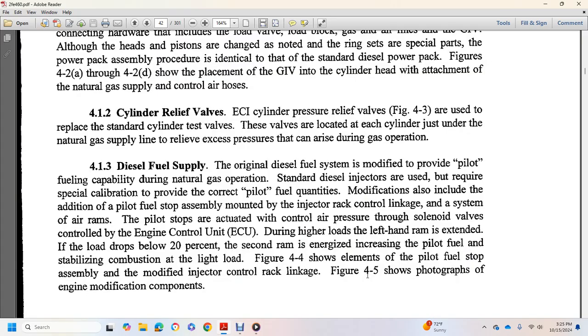4.1.3 The diesel fuel supply. The original diesel fuel system is modified to provide pilot fuel capability during natural gas operations. Standard diesel injection is required with a special calibration provided with the correct pilot fuel quantities. Modification includes the addition of the pilot fuel stop assembly mounted with the injector rack with the control linkage system with the air rams. Pilot stops actuate with the control air pressure with the solenoid valve control with the engine control unit during higher loads.